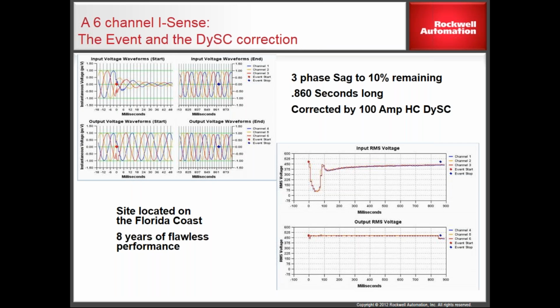Now if I solve this problem with a DySC, it's running 5 seconds a year. If I solve it with a UPS, the UPS is being trickle charged 24 hours a day, 7 days a week, and it's only giving you 5 seconds of protection. It's a 92% efficient device versus a 99.5% efficient device, and that makes a huge difference.